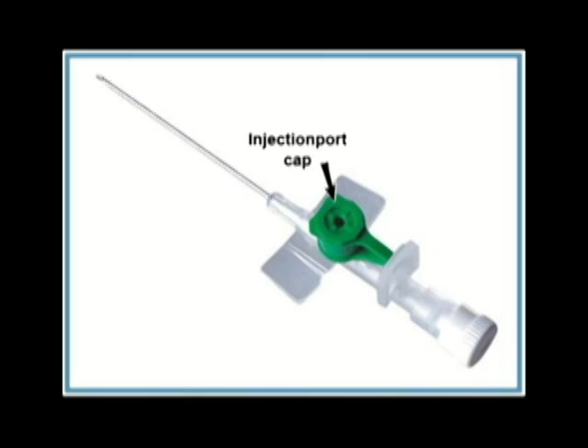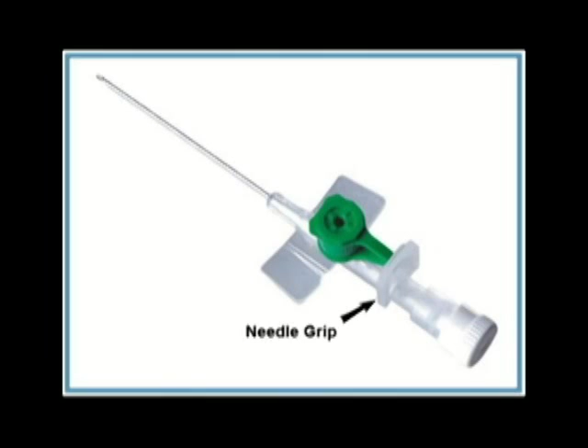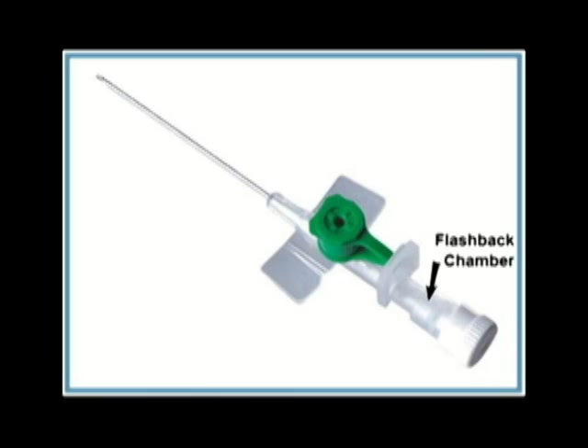The needle grip, or needle hub, is part of the IV cannula, for resting the thumb during a three-point grip, provides stability, and prevents bending of the needle during venipuncture. The needle grip or hub is contoured, to anatomically follow the curve of the thumb. The flashback chamber is essential in an IV cannula, for visual monitoring of blood after venipuncture, confirming correct catheter placement. Inside, it has a hydrophobic filter to prevent backflow of fluids into the chamber. The flashback chamber is also specially designed to prevent spillage of blood.